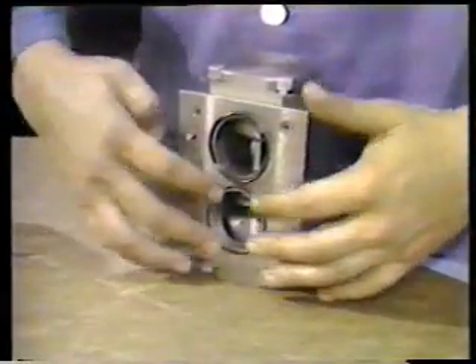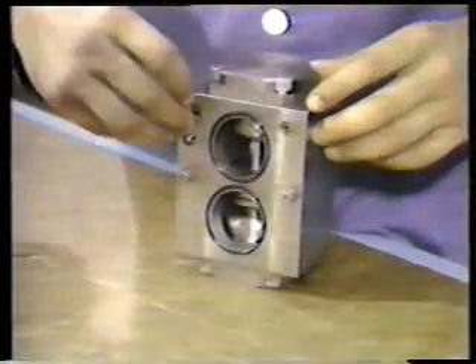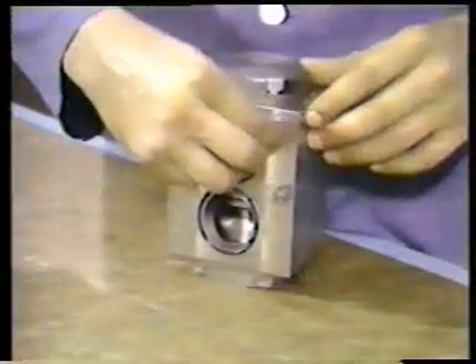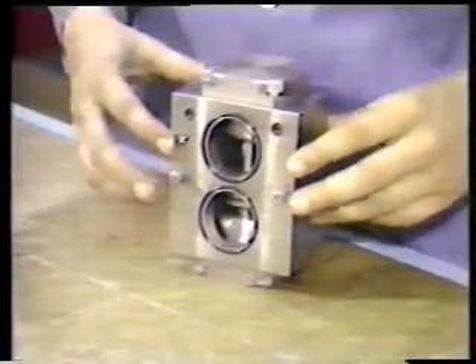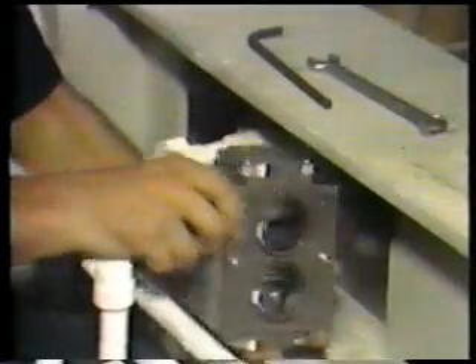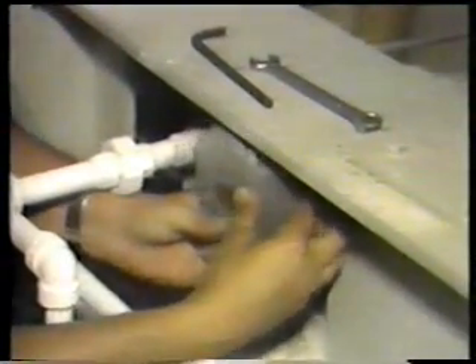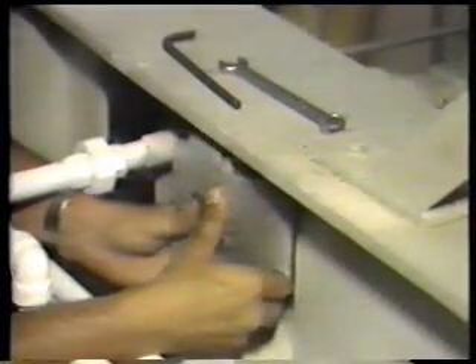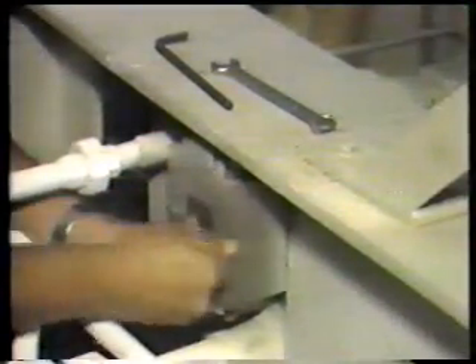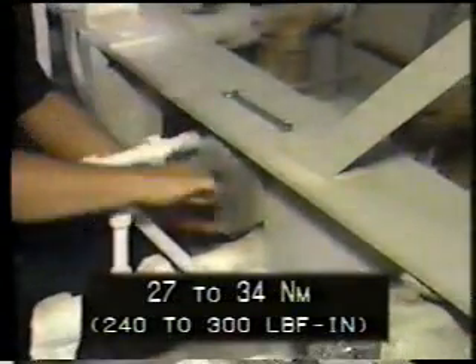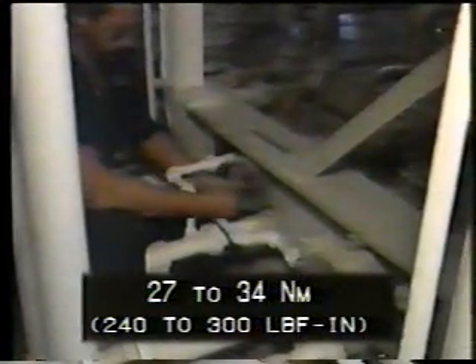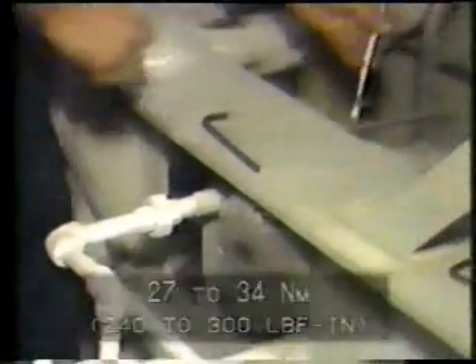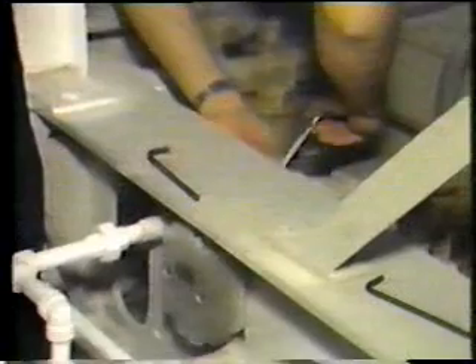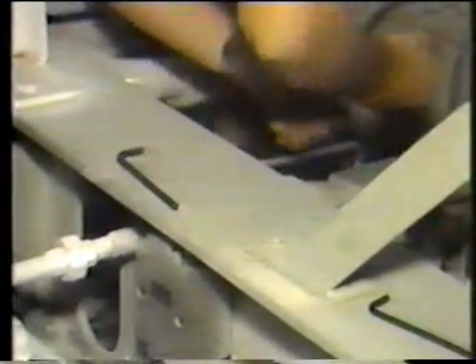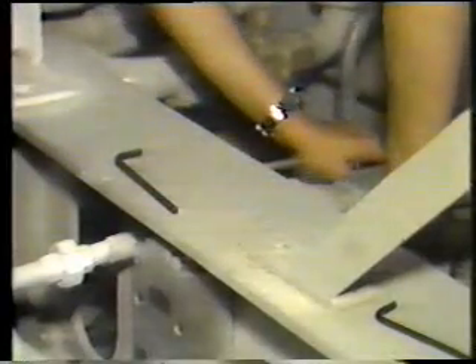On the mounting surface of the valve, install the 4 O-rings. Install the valve on the package by matching the index hole and guide pin on the skid. Tighten the 2 captive screws. Torque the screws to 27 to 34 Newton meters, or 240 to 300 inch-pounds. Reconnect the plumbing used to bleed the system. Tag the valve for the leak test at the end of the fuel system maintenance operations.